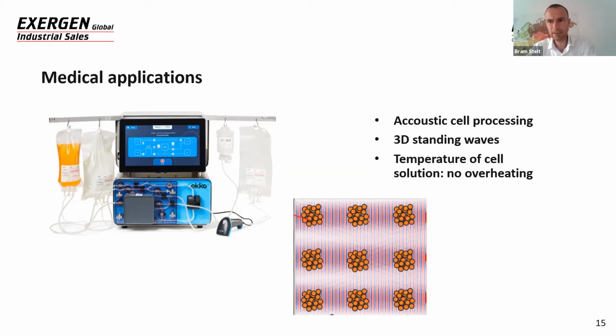Why is temperature needed then? Temperature measurement, that's because by supplying these acoustic waves, the sound waves, you supply energy to the fluid containing the cells, and it heats up the fluid. So they need to make sure that the fluid doesn't get too warm. So it's kind of an alarm system: if the temperature gets too warm, which could potentially destroy the cells, you get an alarm. So that's how our sensor is used in this way.